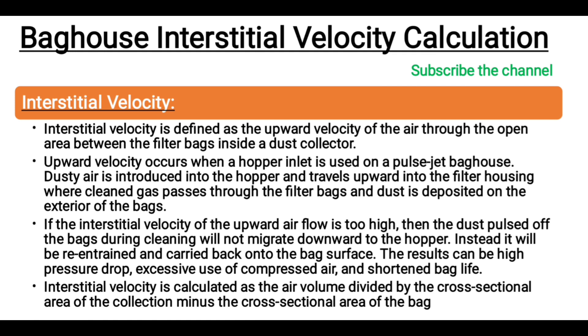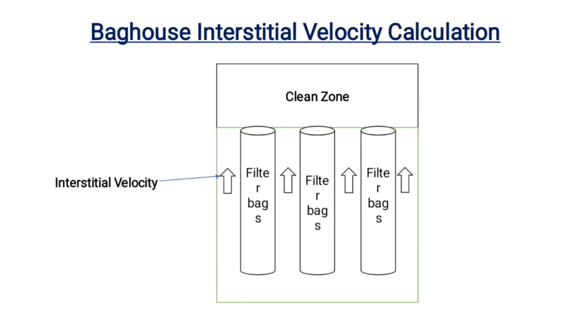How to calculate the interstitial velocity? Interstitial velocity is calculated as the air volume divided by the cross-sectional area of the collection minus the cross-sectional area of the bag. The schematic diagram illustrates this: air volume divided by the cross-sectional area of the collection minus the cross-sectional area of the bag.